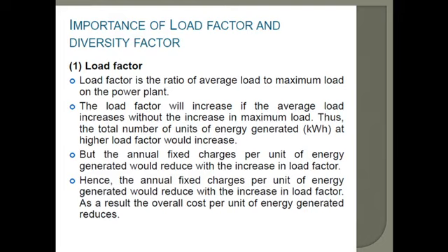Thus, the total number of units of energy generated in kilowatt hour at higher load factor would increase, but the annual fixed charges per unit of energy generated would reduce with the increase in load factor. As a result, the overall cost per unit of the energy generated reduces.